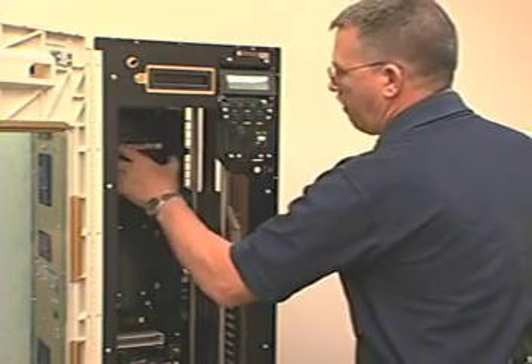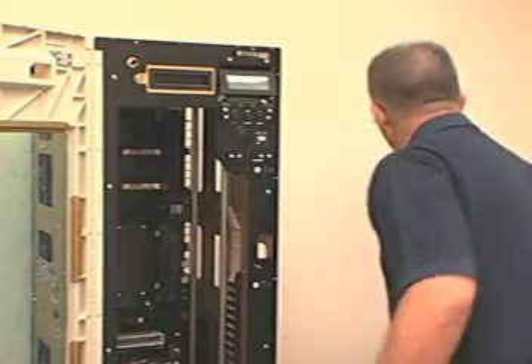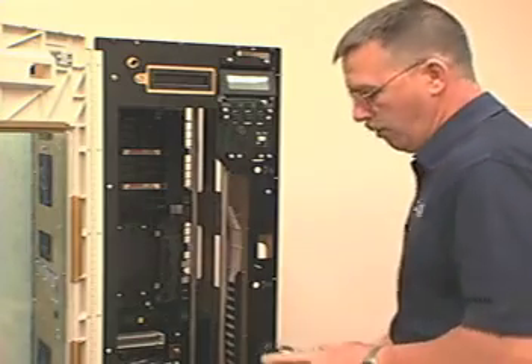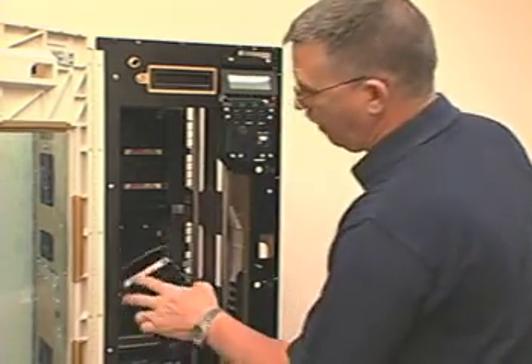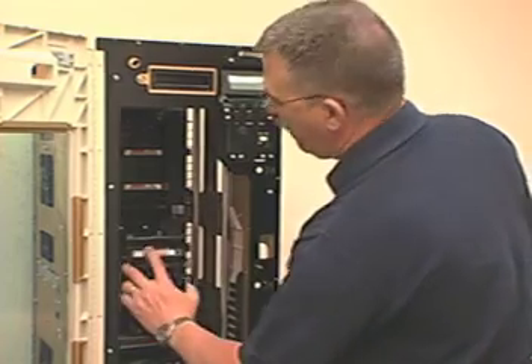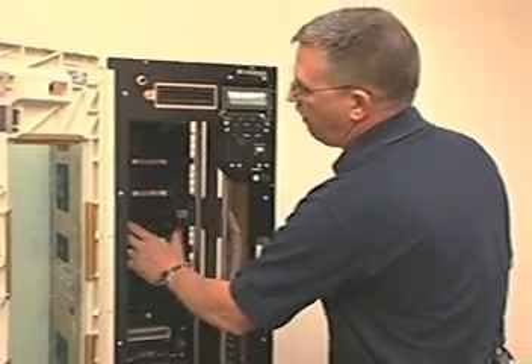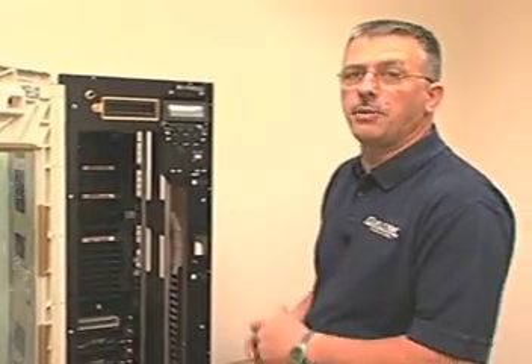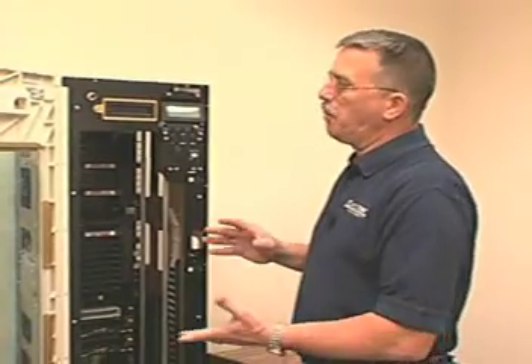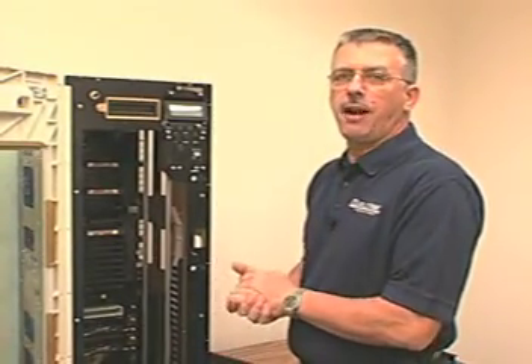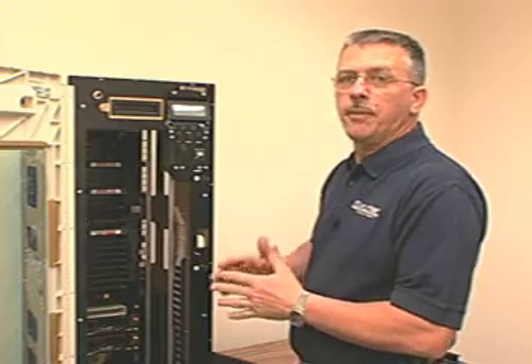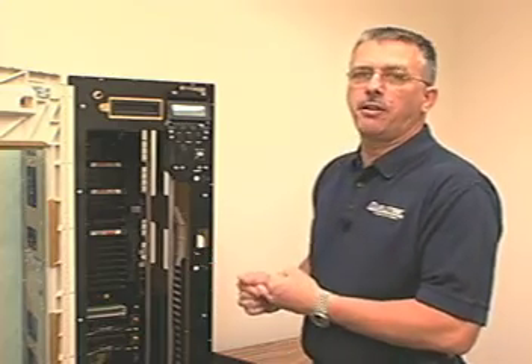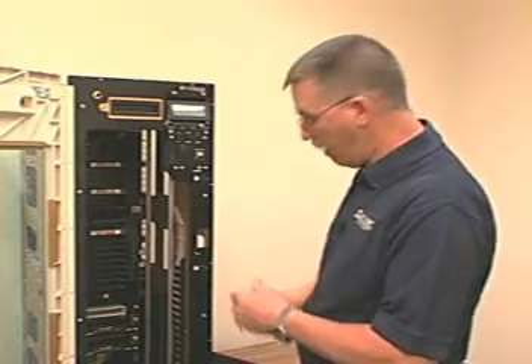A configuration of the library with calibration is always required after you do an upgrade in the field, or anytime you have a failure and you replace something. I always recalibrate the library, because by doing that you put the library back to what's called its 0 state. It knows how many steps and how many turns it takes to get to each position within the library.